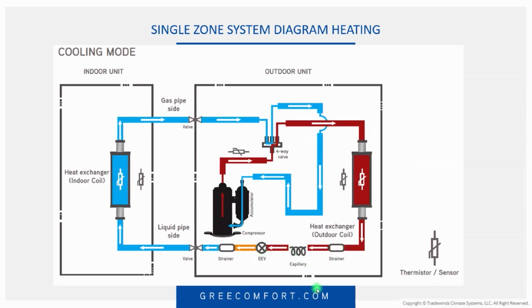Now, as far as the metering devices go, we need to talk about that a little bit. The way we did these diagrams, we show it with an EEV and a capillary. Some of the machines do have an EEV and a capillary. Some of them will have only a capillary, and some of them will have an EEV only. It depends on the machine you're working on, and how the manufacturer made it, how GREE made it.